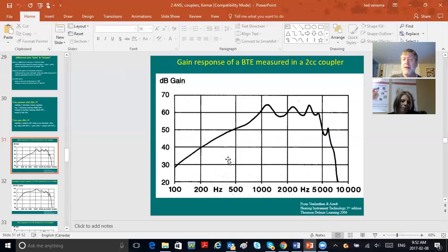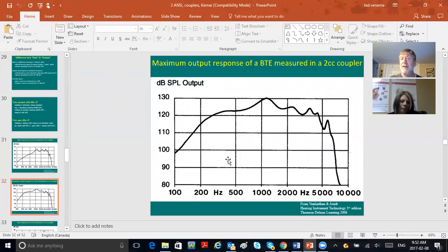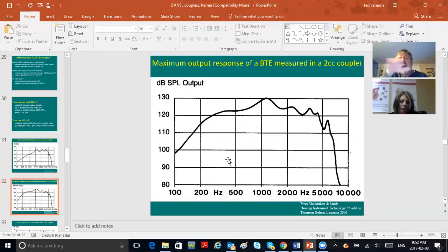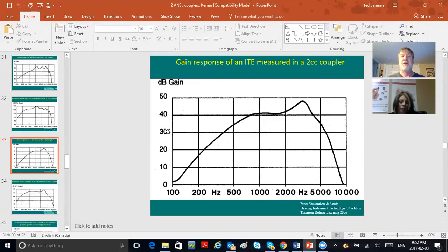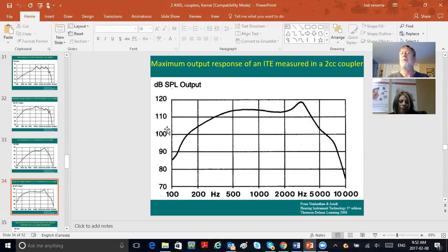When you look at an OSPL 90 by contrast, it's more like everything is bloated—everything is saturated, you've got a flatter frequency response, and the numbers are now over 100, which confirms it's output. Input plus gain equals output. Here's the gain response of an ITE in a 2cc coupler, and here's the maximum power output of the same ITE in the 2cc coupler.